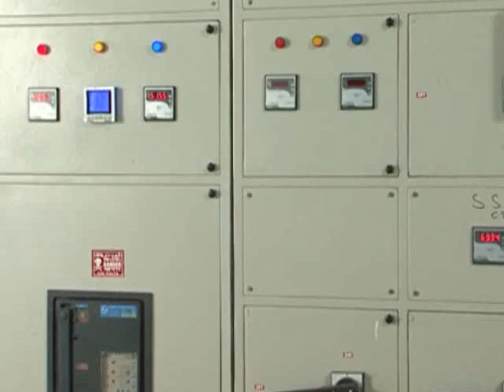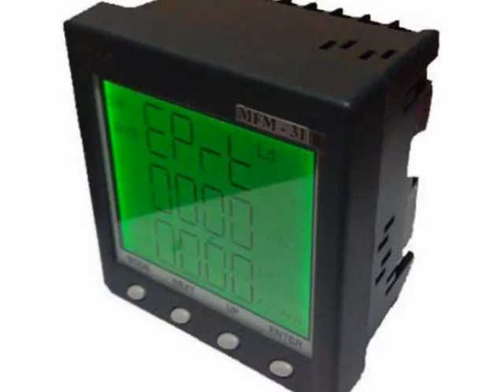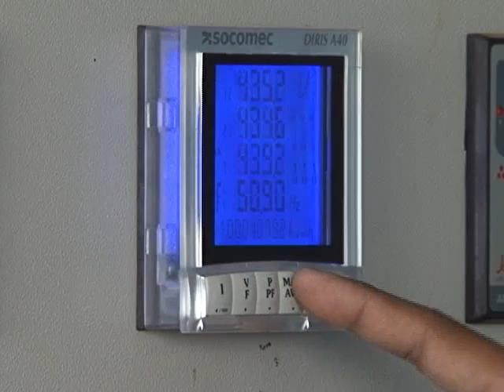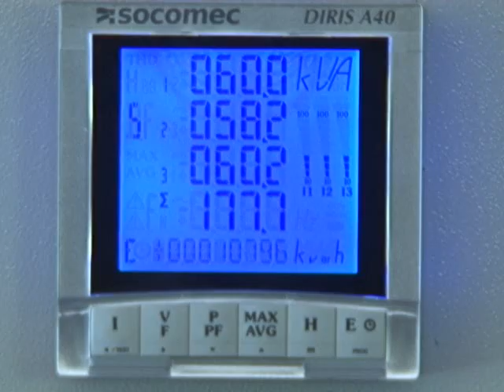MD controller. The electricity power allotted to any factory is pre-decided as per demand. It is advisable to utilize the energy within this limit to avoid further inconveniences. So here is an important recommendation: the MD controller. The MD controller is a device to control the electricity consumption as per the maximum demand. Using this device, we can set the maximum limit of usage in kVA. The MD controller continuously records the electricity used after a stipulated time interval. Using these readings, we can manage the power usage in the factory.